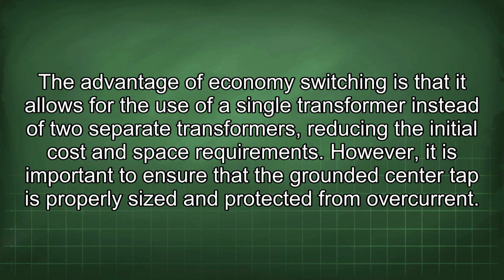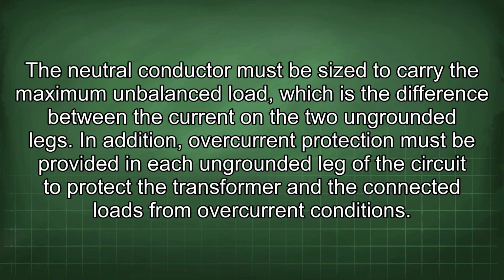However, it is important to ensure that the grounded center tap is properly sized and protected from overcurrent. The neutral conductor must be sized to carry the maximum unbalanced load, which is the difference between the current in the two ungrounded legs. In addition, overcurrent protection must be provided in each ungrounded leg of the circuit to protect the transformer and the connected loads from overcurrent conditions.